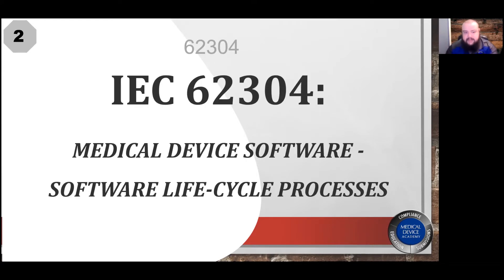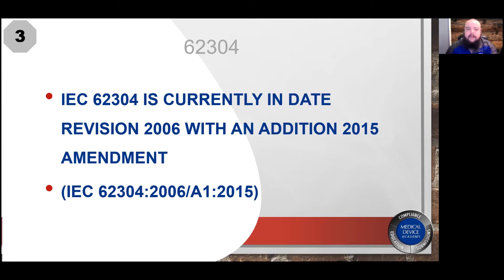62304 is an international standard published by the International Electrotechnical Commission — it is the standard for medical device software lifecycle processes. IEC 62304 is currently at the 2006 date revision and has an additional amendment released in 2015. The full title should be IEC 62304:2006 plus A1:2015, to include both the standard and the 2015 amendment.